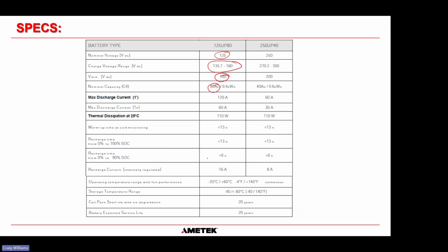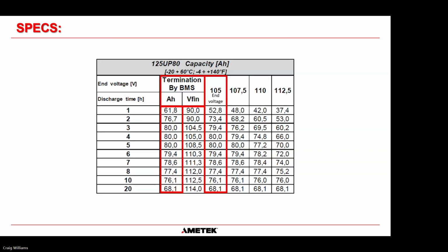And it tells us here that the capacity is 80 ampere hours and the maximum current you can get out of this system is 120 amps. So it tells you all the stuff that you need to know for the battery on the data sheet. But what's kind of confusing about the salt battery is how they do their battery capacity. So we've got our discharge times on the left here. We've got 1 hour down to 20 hours, okay? And they're saying that this column here is the termination by the BMS. And what that's saying is, that's not getting to this 105 volt end of voltage. That is the BMS actually terminating the discharge, okay? It will actually disconnect the battery after these times.